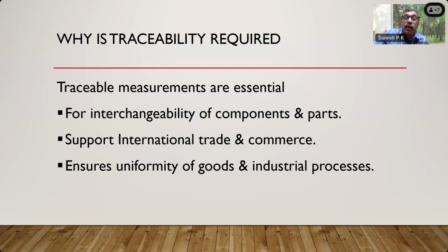There is a question whether any tolerance is allowed in the measurement. Yes, tolerance is allowed as per OIML R117 for flow measurement. You have different classes of measurements, and tolerances are specified in OIML R117. OIML R117 is freely accessible from the OIML site. You can download it and look for tolerances for various kinds of fluids or measurements. It ranges, if I remember, from 0.2% to some 2%, or 1.5%, something like that, for various kinds of measurements. So tolerance is allowed, and tolerance is required also.